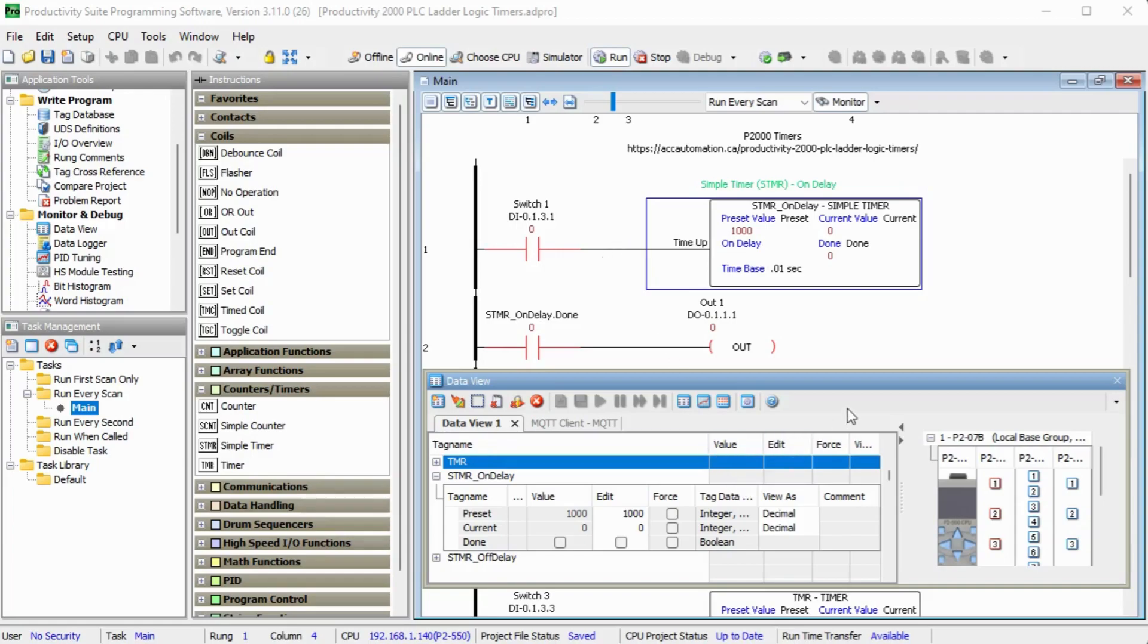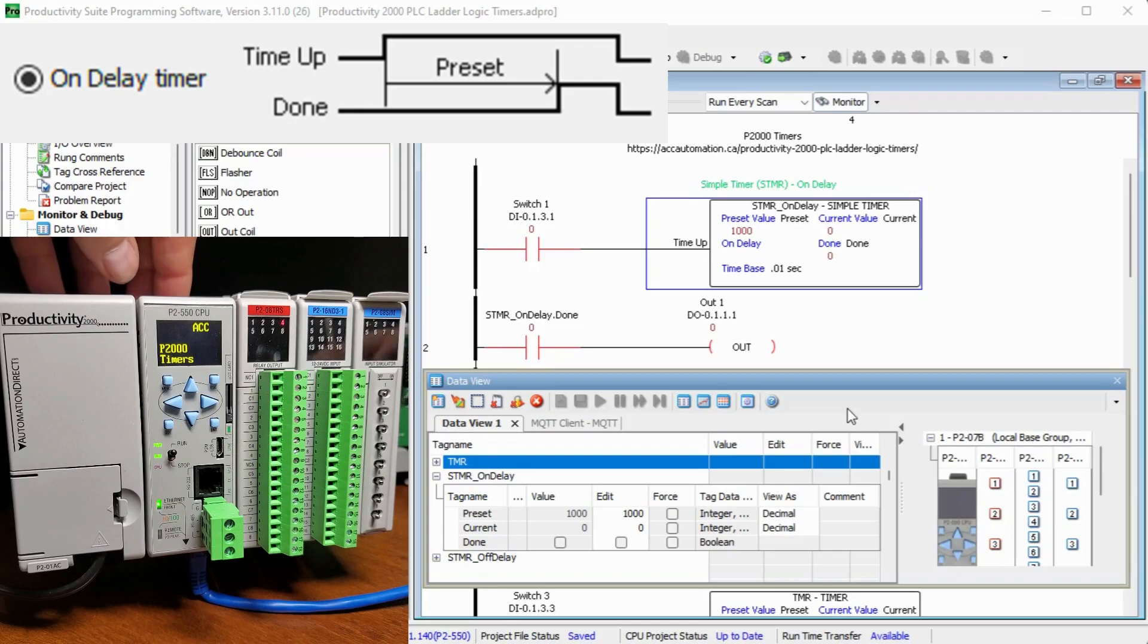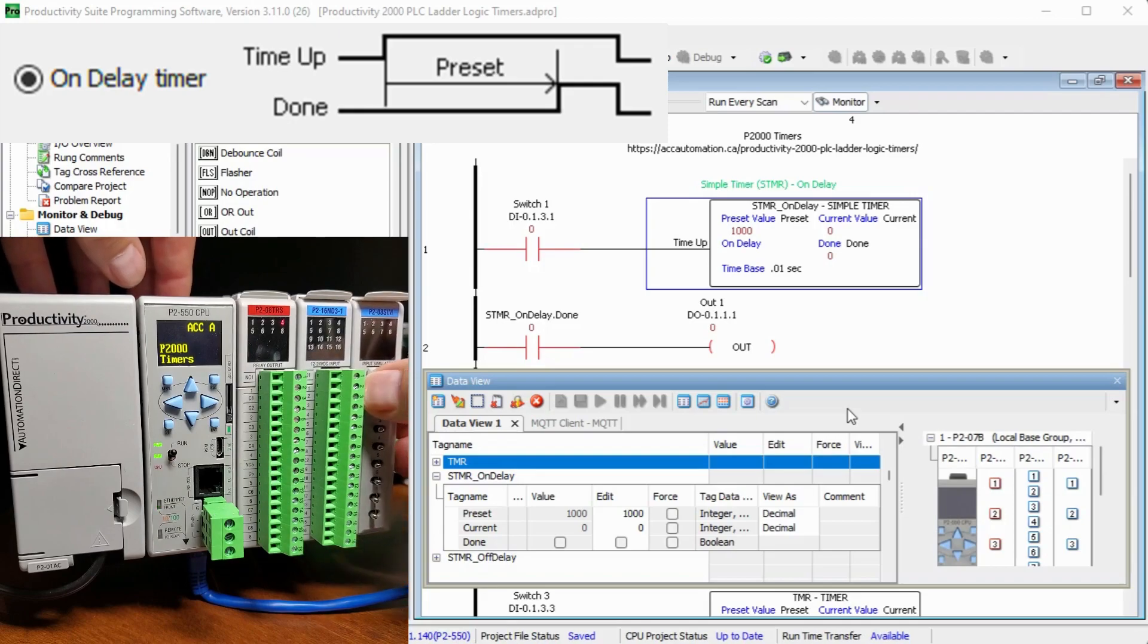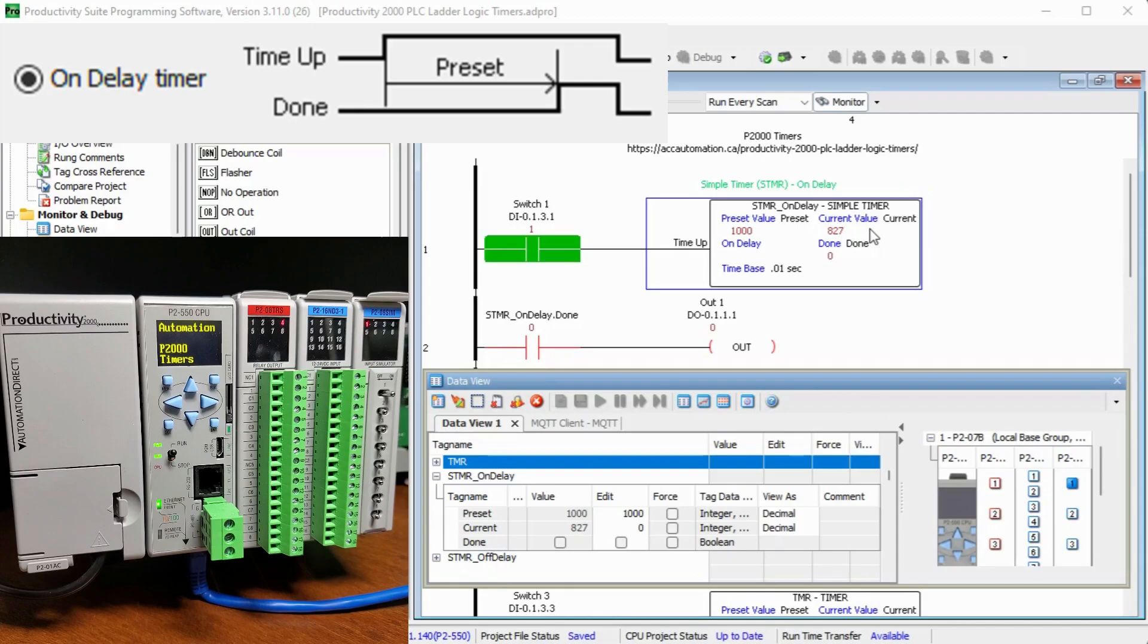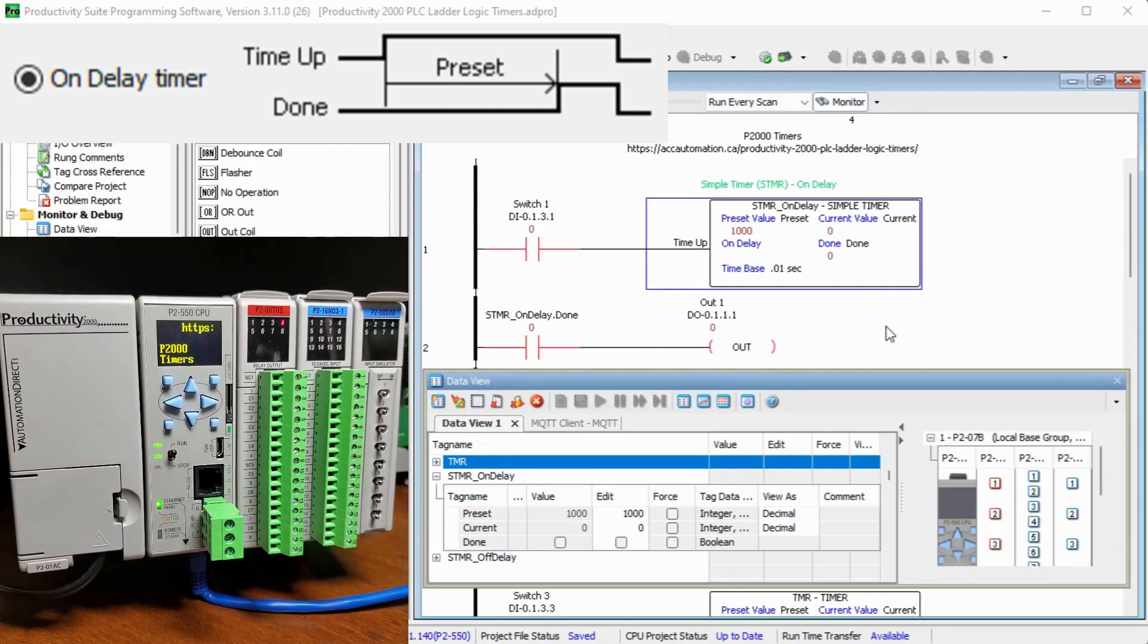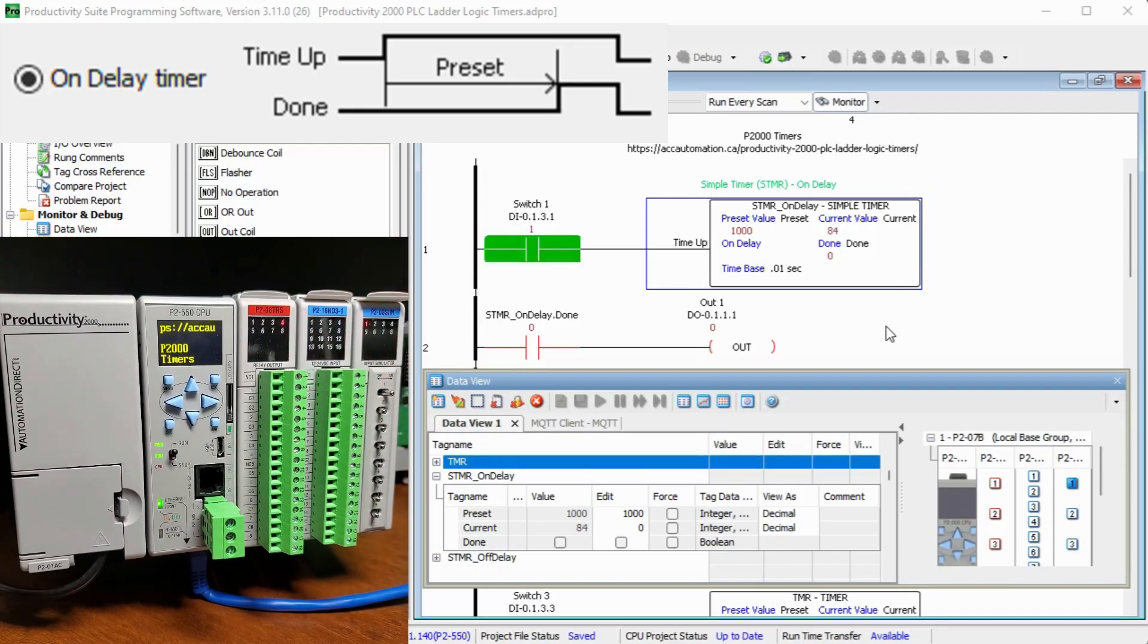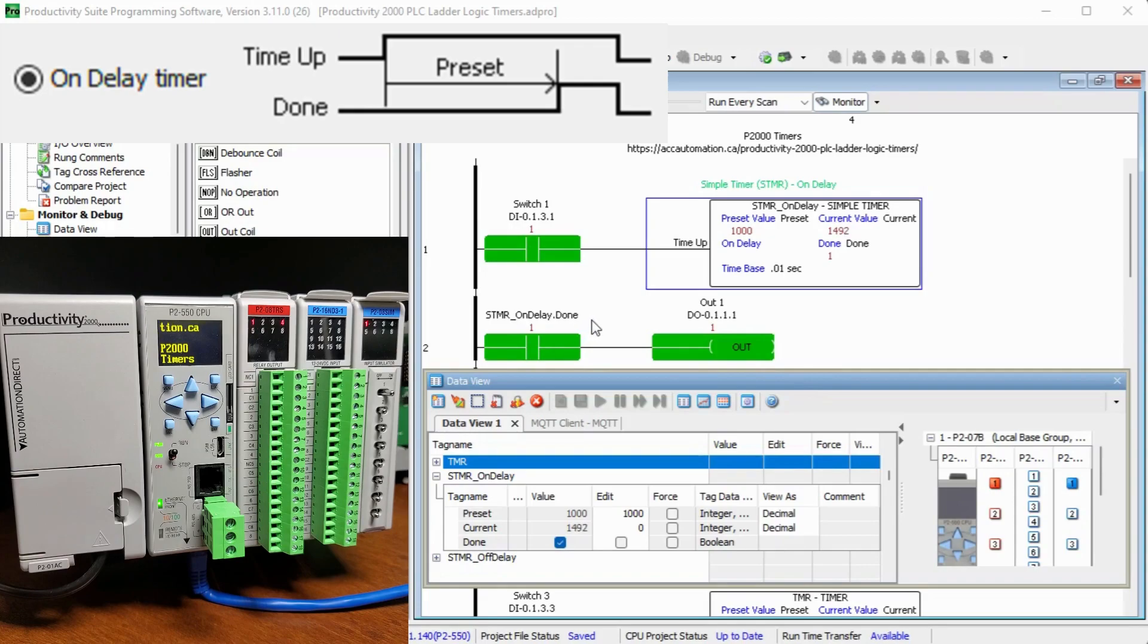So if we look back to our hardware here and we turn on the first switch, we can now see it timing up. And as soon as the timing up according to the diagram is over, it turns on the output, which it exactly will do. Now, if I turn off that switch, then the output turns off. And so once again, turn the switch on. We have our timing and you can see in the timing chart, how that works. As soon as it hits the set value, it turns the output on, off of this done bit. And then we can turn it back off.